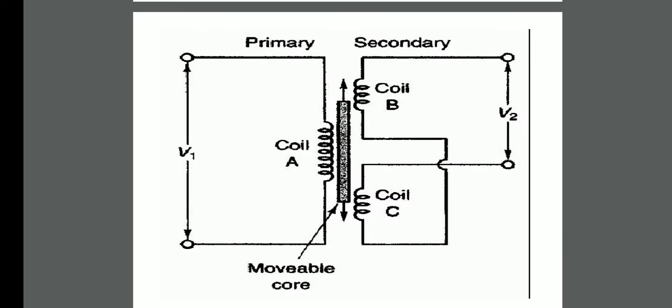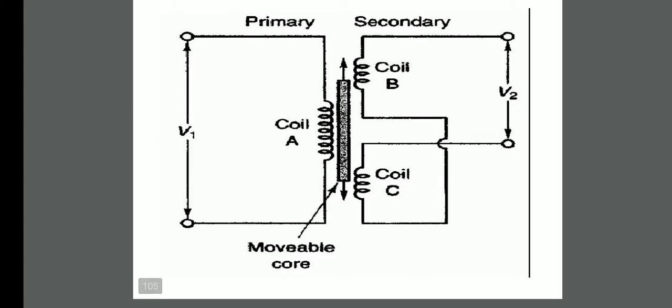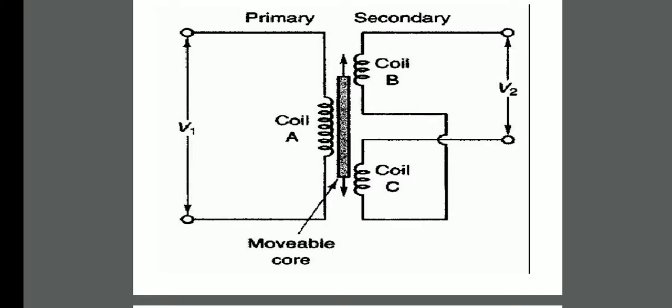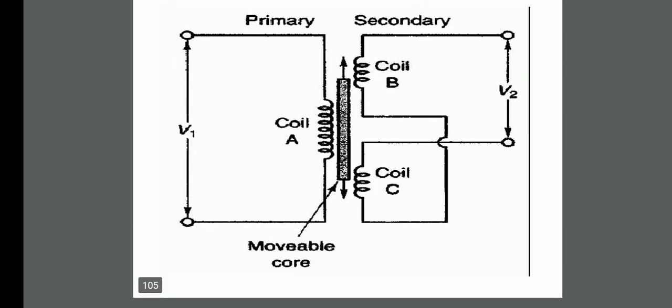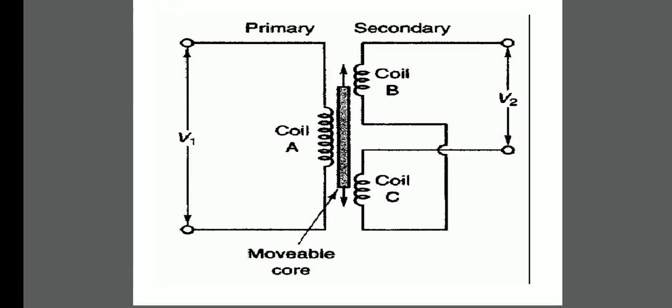The principle works like this: whenever we apply an AC voltage across the primary winding — V1 voltage is applied across coil A, which is the primary winding — there will be a change in flux in the air gap due to alternating current. That change in flux induces an EMF in both secondary coils B and C. That is what is called mutual inductance. The output voltage from coils B and C is represented as V2, which gives the measure of the displacement at the point under reference.